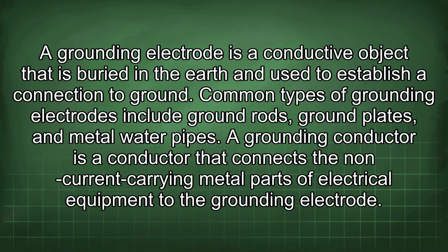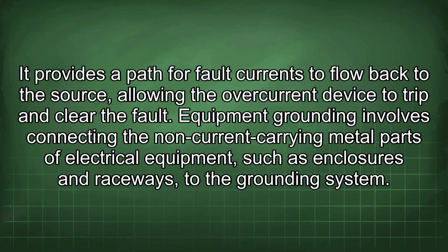A grounding electrode is a conductive object that is buried in the earth and used to establish a connection to ground. Common types of grounding electrodes include ground rods, ground plates, and metal water pipes. A grounding conductor is a conductor that connects the non-current carrying metal parts of electrical equipment to the grounding electrode. It provides a path for fault currents to flow back to the source, allowing the overcurrent device to trip and clear the fault.